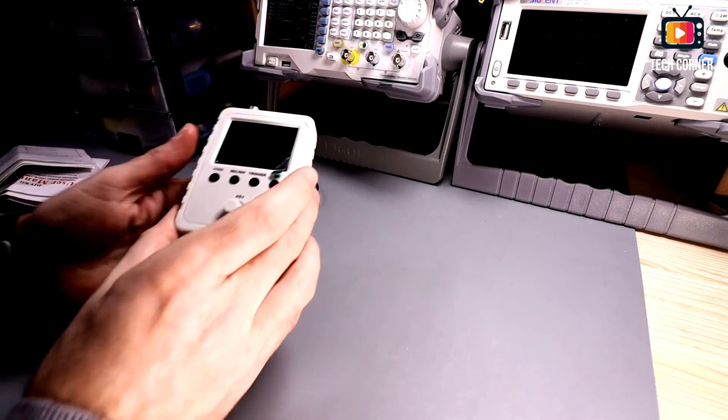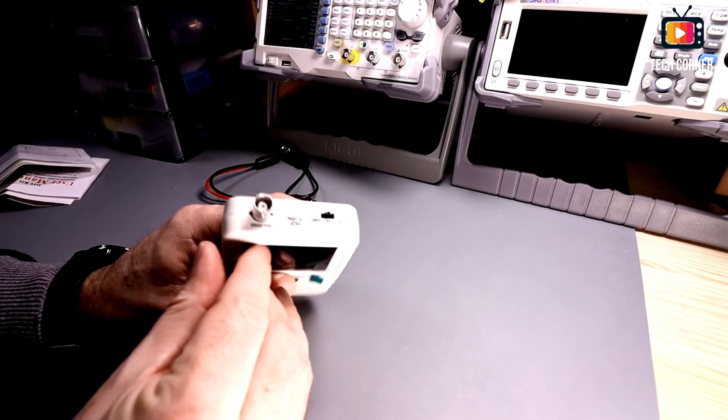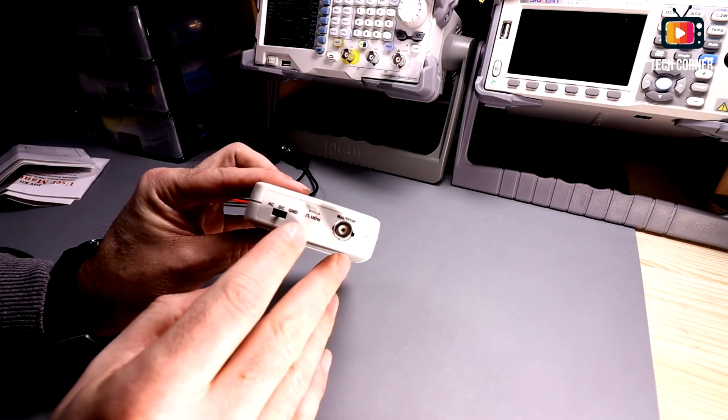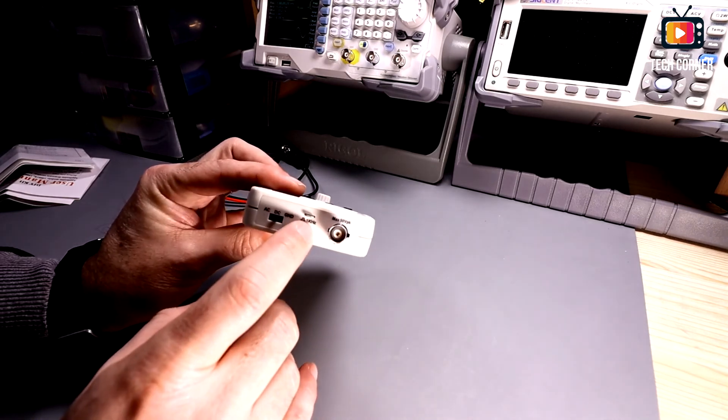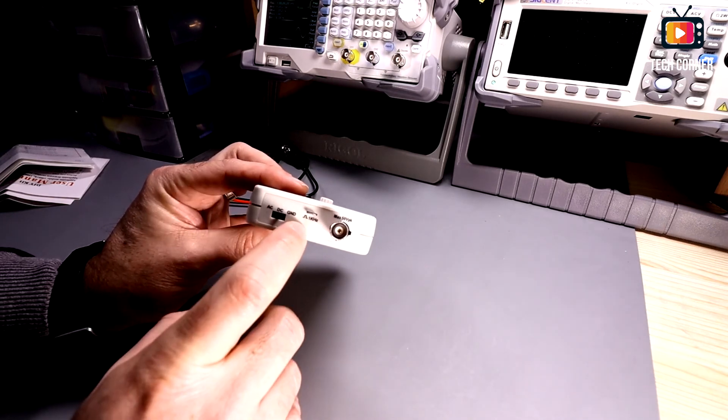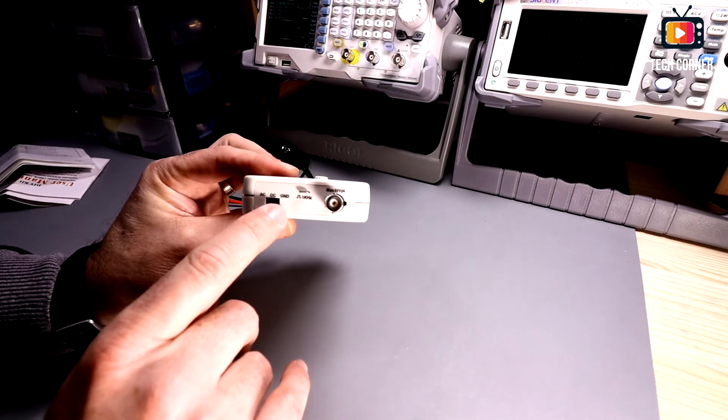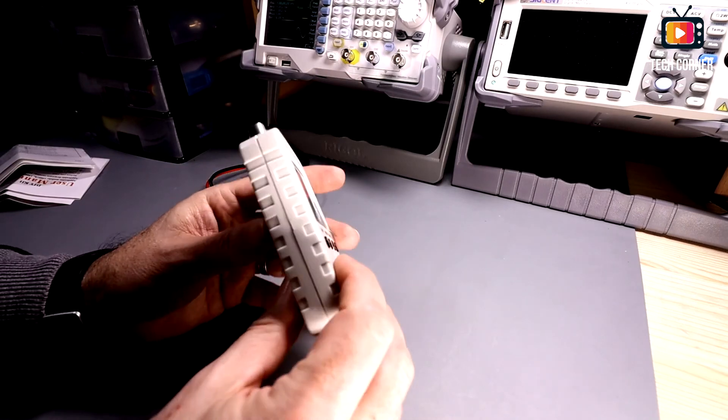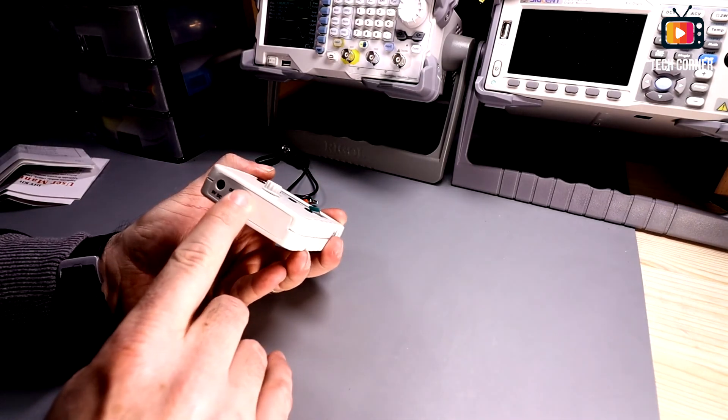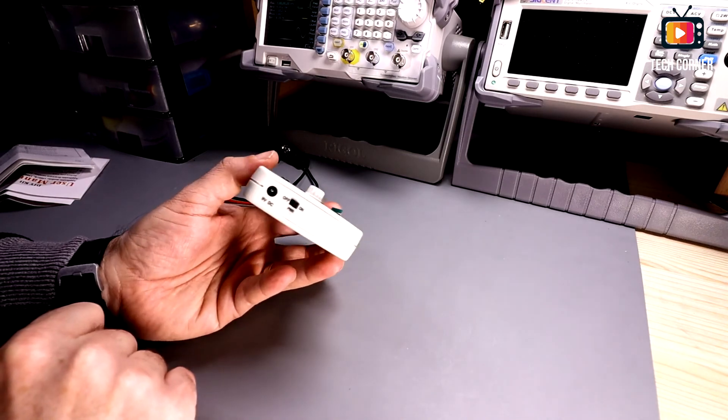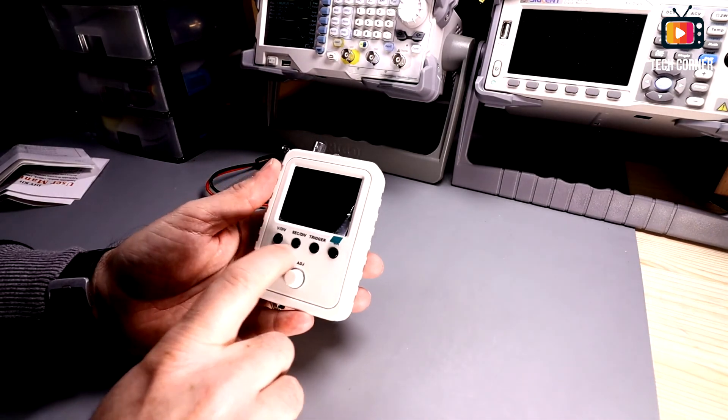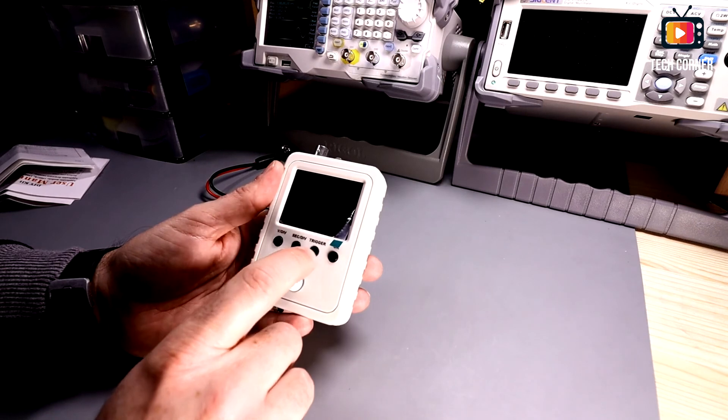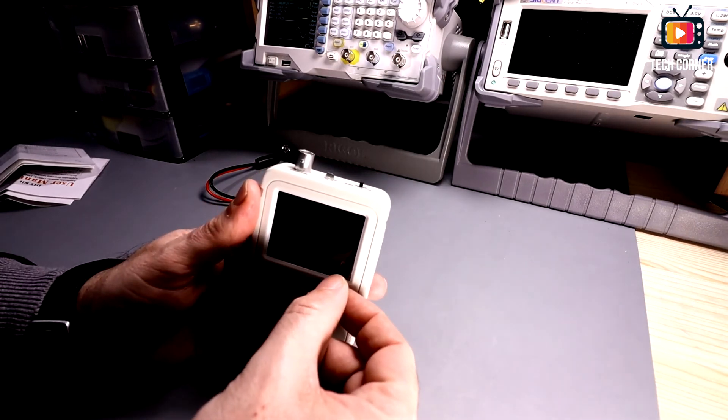So in this device we have on the top the BNC connector. We also have here a square wave generator for calibration and for test. On the left it has the coupling switch where we select AC, DC or ground. Let's leave it in DC for now. On the back we have the on off switch and the power supply socket. In the front it has four buttons and the knob. The vertical position, the horizontal position, the trigger button and the hold button.